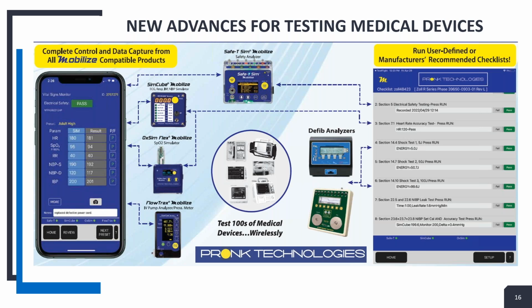The report at the end shows you everything that we would have done for that procedure. At the top is header information of who the organization is. It lists every device we used to do the testing: what safety analyzer we used, the model, the serial number, the calibration date of it, the calibration date of the SPO2, the calibration date of the defibrillator. So anything you used, that calibration information is on the report, which saves you the hassle of having to go find out those cal dates. If you ever have an auditor come in and they want to see your service history, the next thing they're going to ask is, well, show me the calibration dates on your devices. So it's all there on the report.